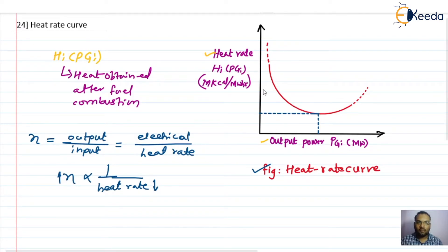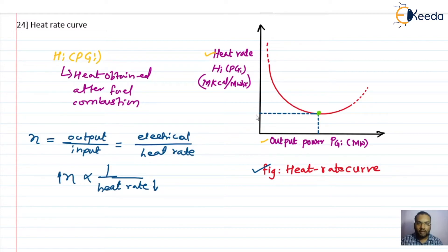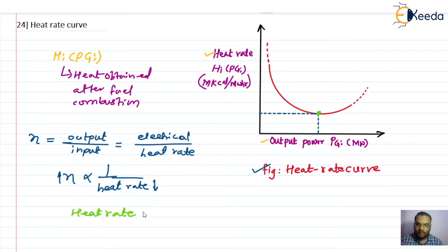From the graph we can see that the efficiency will be maximum at the point where we are giving the minimum heat rate and getting the maximum output power. Taking a typical example, this heat rate value is typically around 2.5 Mega kilocalories per megawatt-hour.